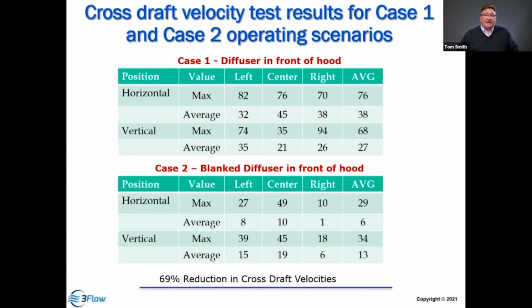When we blanked off the diffuser, it went down to 29, 34, a 69% reduction in cross-draft velocities. So that diffuser orientation, the type of diffuser and its proximity to the hood, was causing high cross-draft velocities interfering with the containment capabilities of the hood. We'll show that in more detail later.